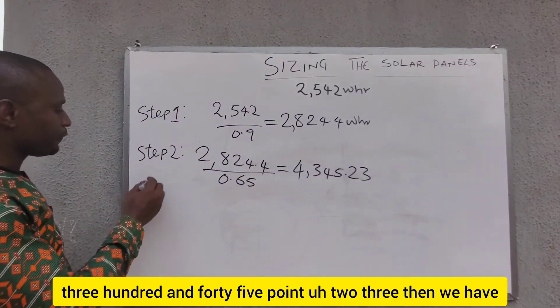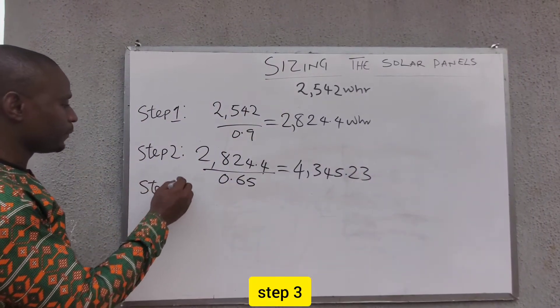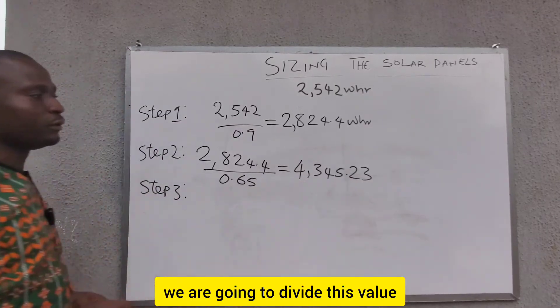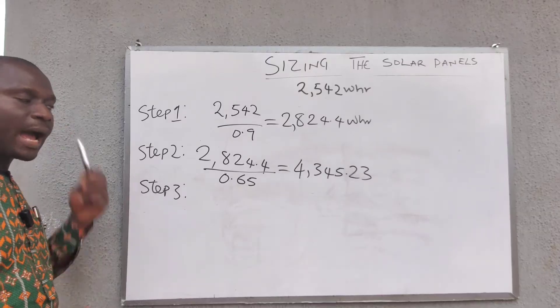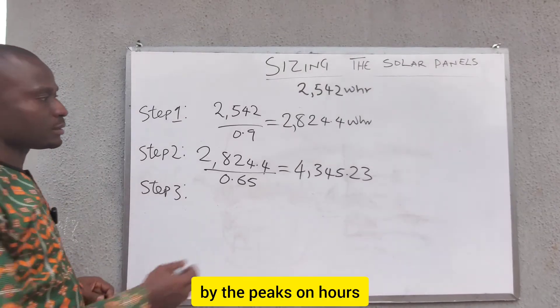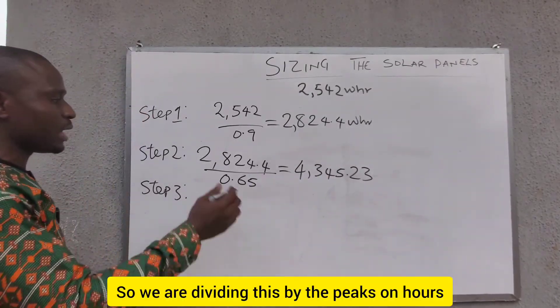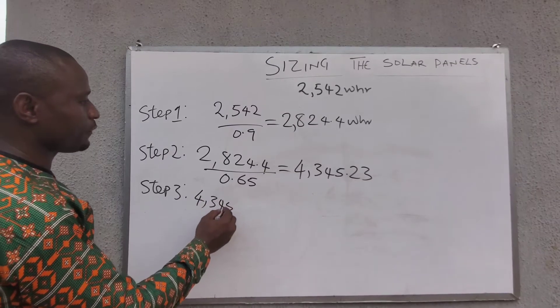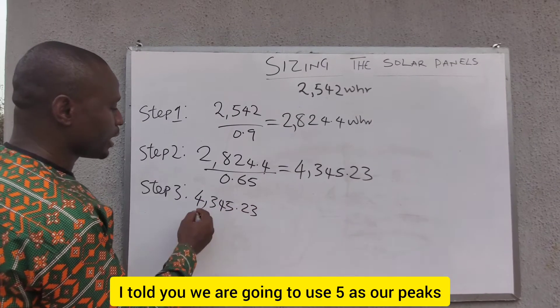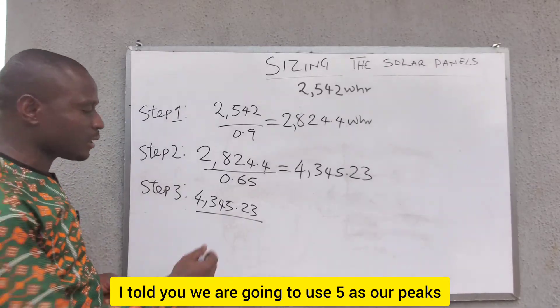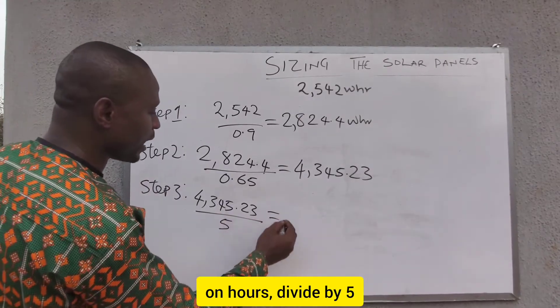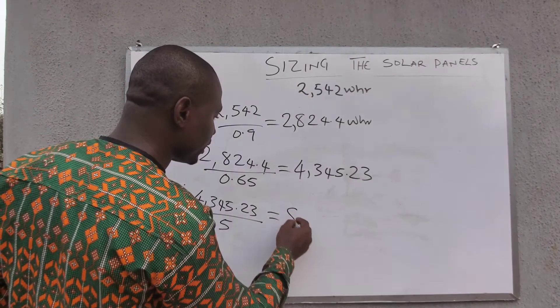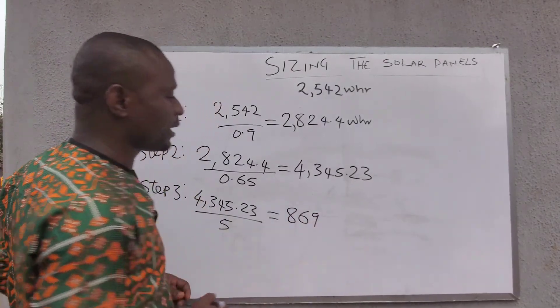Step 3: divide the Step 2 result by the peak sun hours. We are using 5 hours. So 4,345.23 divided by 5 gives us approximately 869 watts.